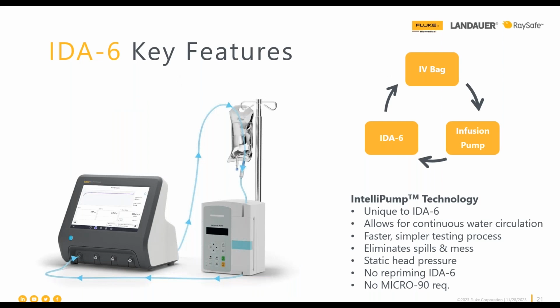Just one last thing I wanted to highlight here is the IntelliPump technology. That's the ability to run circulated water through the system. It has a reverse pressure sensor on the outlet side. It allows the water to run through the inlet of the pump, the front of that channel, through the device, which measures the flow and volume. Then it has the ability to pump water back up into an IV bag or a reservoir and continuously flow through. Because it has this pressure sensor in the backside, there's no issue of it throwing off the results. So this really does allow for a much cleaner, simpler process.